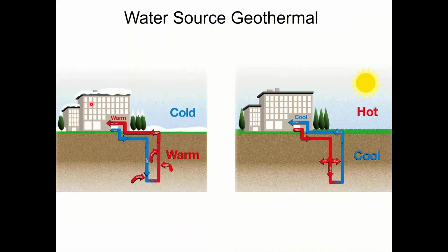Now, if I don't have a large disparity between my heating and cooling needs on an annual basis, like if you're in Atlanta, it just works, right? I have as much heating that I need, as much cooling I need, so I throw all the heat in the ground all summer, and I take it all out all winter. Sounds great. Well, if I'm in the north half of the country, I have more annual BTUs of heating than I need of cooling. So in those cases, what I'll do is put a small boiler in to supplement the loop. So I'm getting all the heat out of the earth. Everything's great. I'm barely ever having to run the boiler. And then maybe by the time I get to March, I have to run the boiler a little bit more, right? So I'm going to size this for the smaller of the two needs, heating or cooling, which means that I am going to have a boiler supplement.